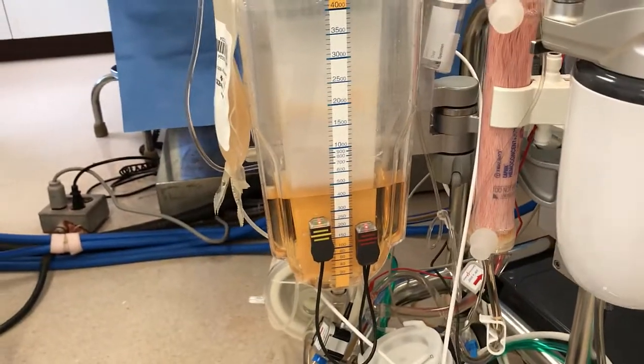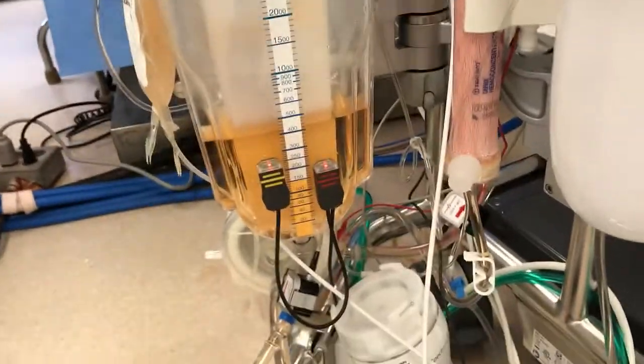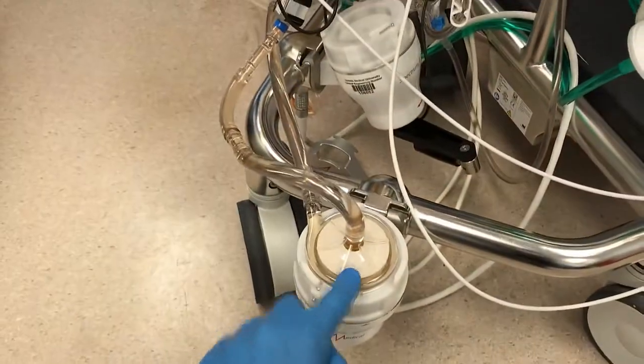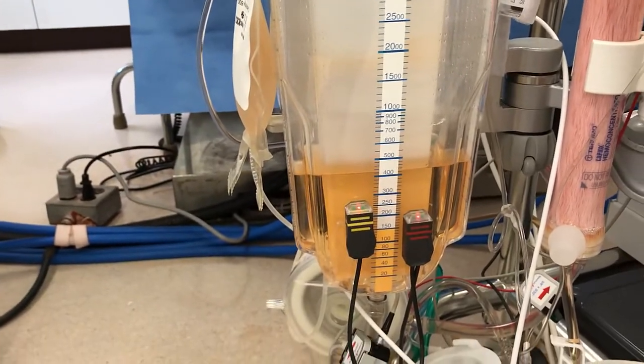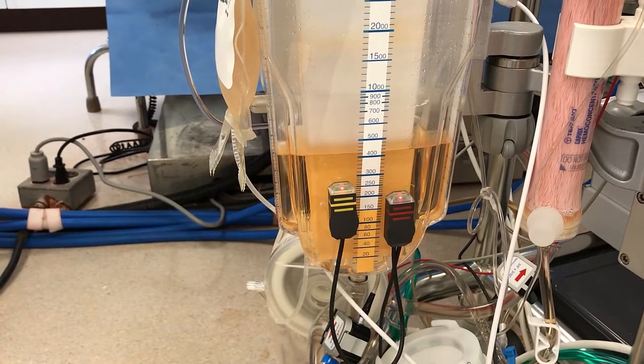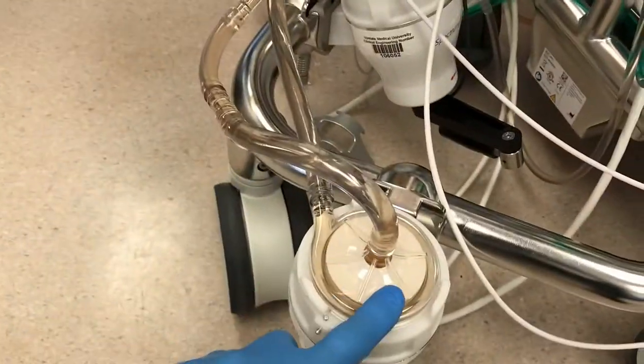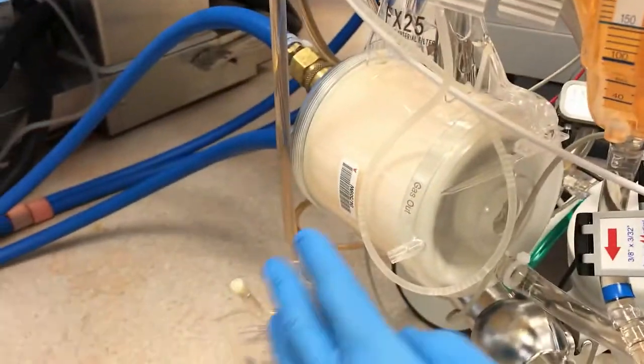The reservoir would be the bucket where we're going to collect the patient's blood. Only we're not collecting it so much as we're circulating it through that bucket. As fast as it comes in the top, we're draining it out of the bottom with this pump. So that flow right now happens to be sitting still, but later on there might be 5 liters a minute of flow flowing through there. So the blood comes down into the pump. We push it out of the pump and over to an oxygenator.